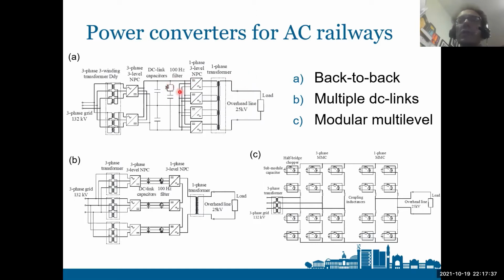Also, we can note that there is this filter in here at 100 Hertz, which is a resonant tank, which is helping to limit the oscillation across these capacitors. Obviously, this filter is tuned at 100 Hertz for 50 Hertz railway, and it will be 33 Hertz for 16 and 2/3 Hertz railway.